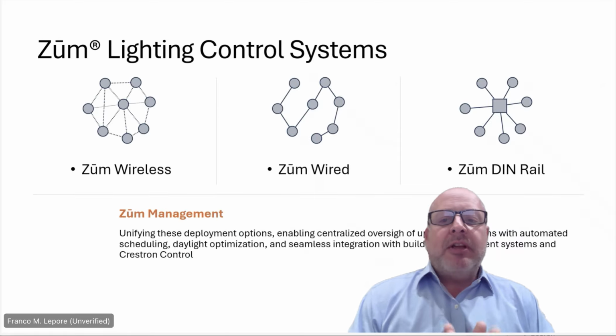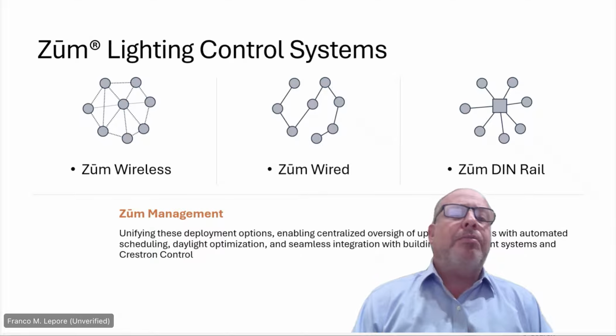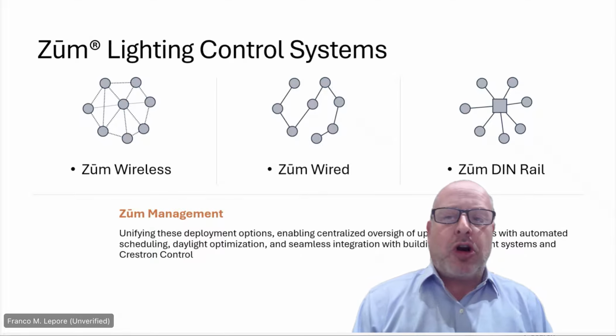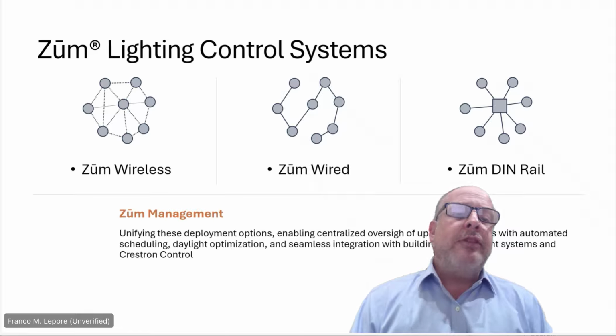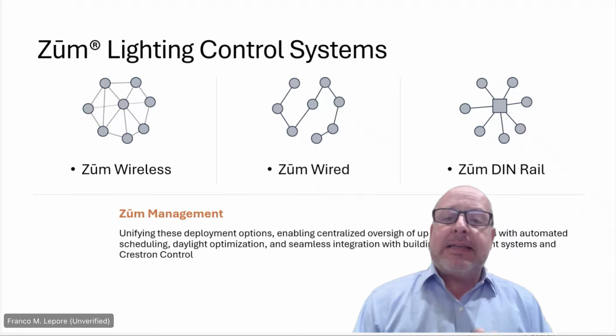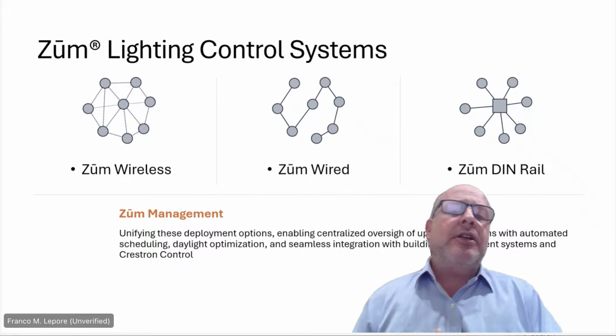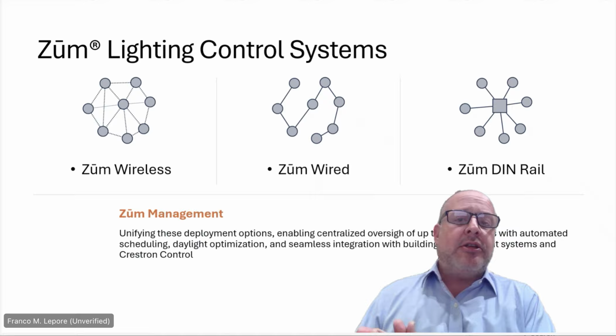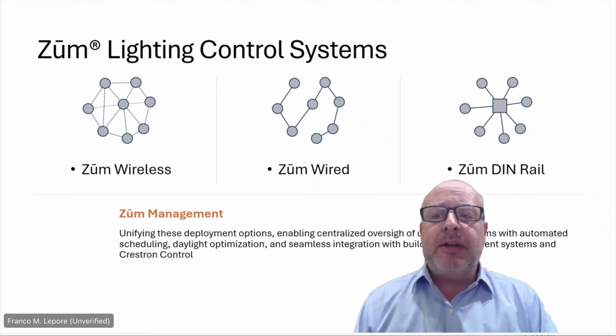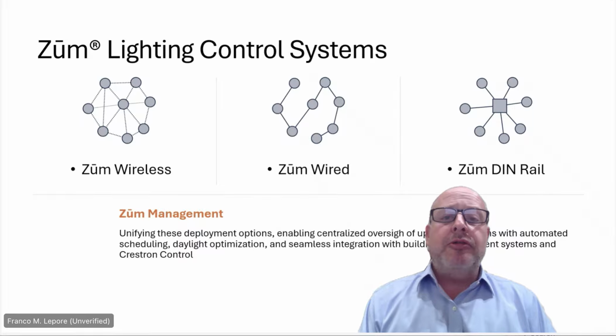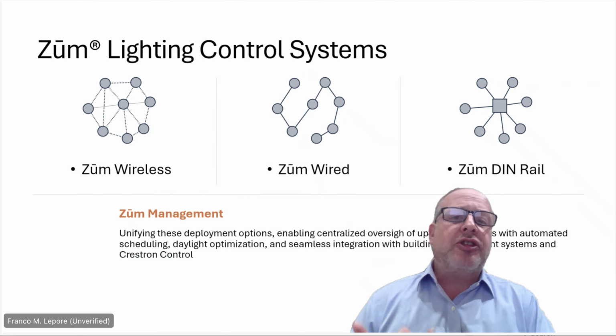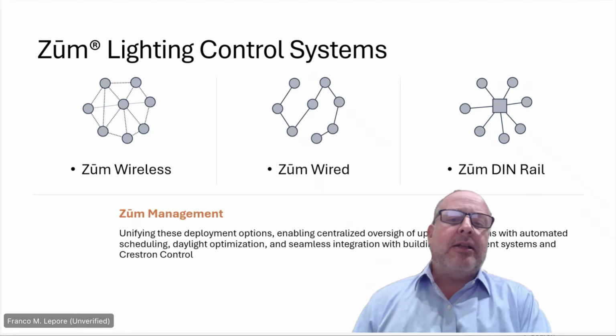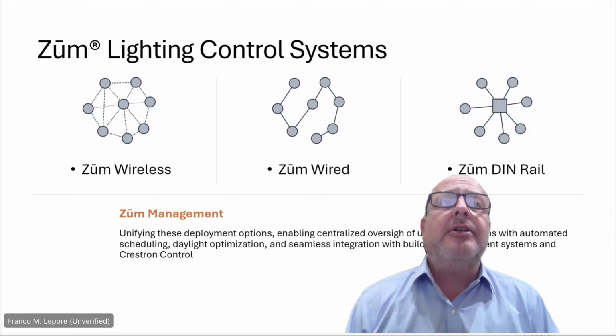In addition to that, each one of those spaces has 9 BACnet objects that we provide at no additional charge, giving you a total of 9,000 BACnet licenses or objects that you can use to integrate smoothly into your building management system. Your building management system can pull cues, get information, access, or even change scenes, turn on and off lights, and do additional scheduling if there's something outside the realm of what the actual processor does.